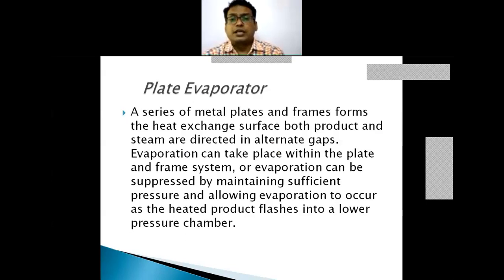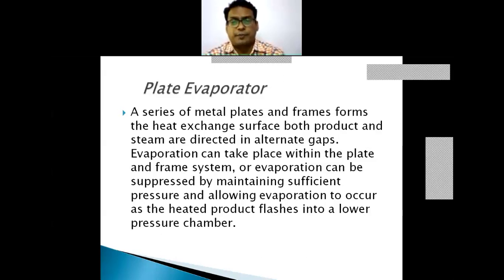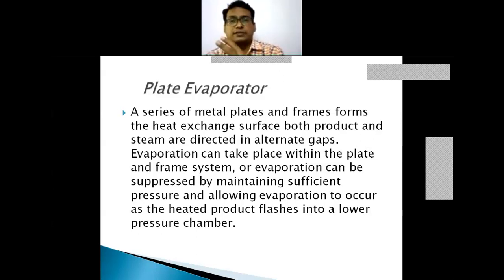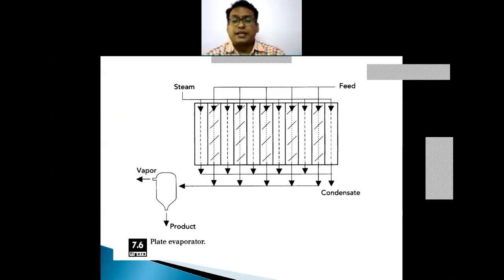Plate evaporators use a series of metal plates and frames. Evaporation can take place within the plate and frame system, or it can be suppressed by maintaining sufficient pressure and allowing evaporation to occur as the heated product flashes into a lower pressure chamber. Flashing means a high-pressure fluid entering a low-pressure vessel causes immediate separation of vapors and liquid if there is sufficient pressure difference. This is the plate frame evaporator system.